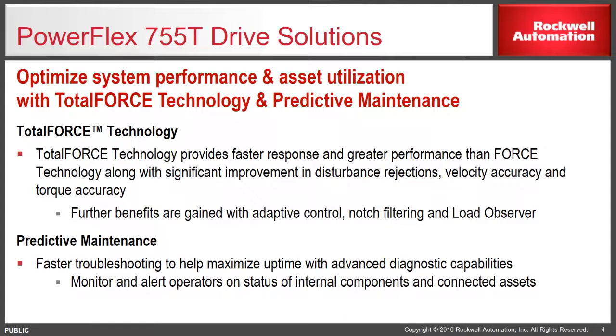The PowerFlex 755T uses a new technology called Total Force and also supports predictive maintenance. Total Force technology offers faster response and greater performance than force technology, along with significant improvement in disturbance rejections, velocity accuracy, and torque accuracy. Further benefits are gained with the use of adaptive control, notch filtering, and load observer. The 755T also contains predictive maintenance, faster troubleshooting to help maximize uptime with advanced diagnostic capabilities. You can monitor and alert operators on the status of internal components within the drive.